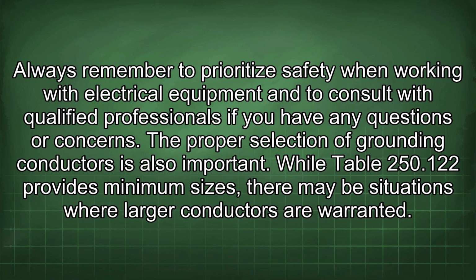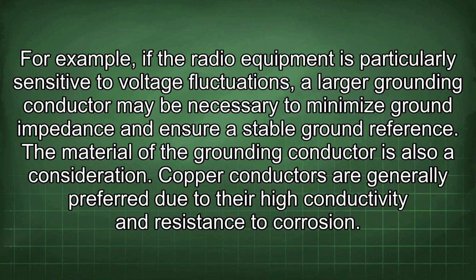While Table 250.122 provides minimum sizes, there may be situations where larger conductors are warranted. For example, if the radio equipment is particularly sensitive to voltage fluctuations, a larger grounding conductor may be necessary to minimize ground impedance and ensure stable ground reference.